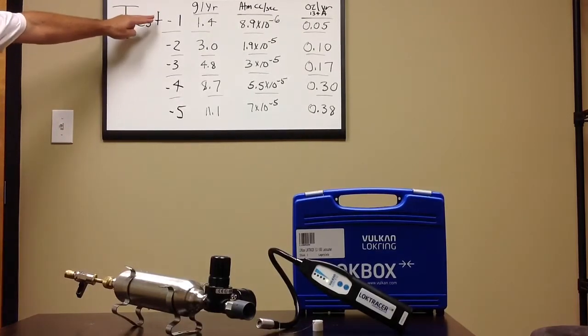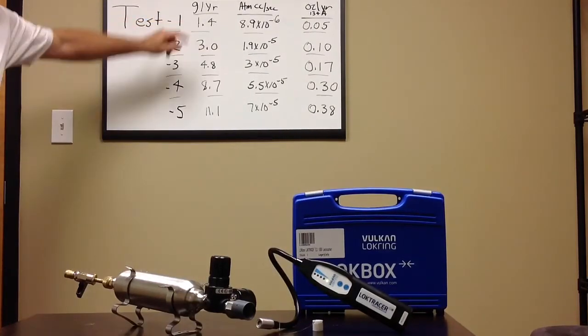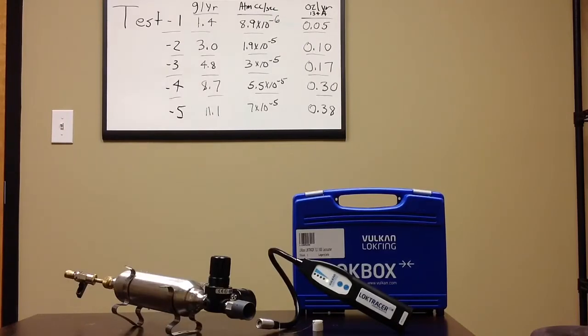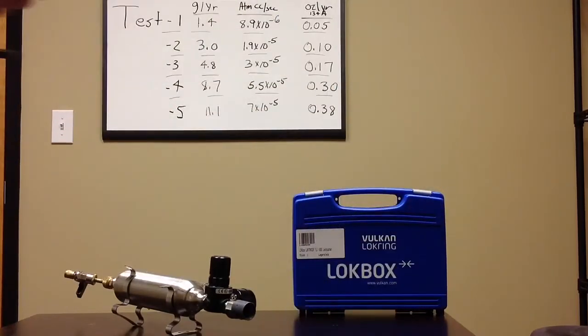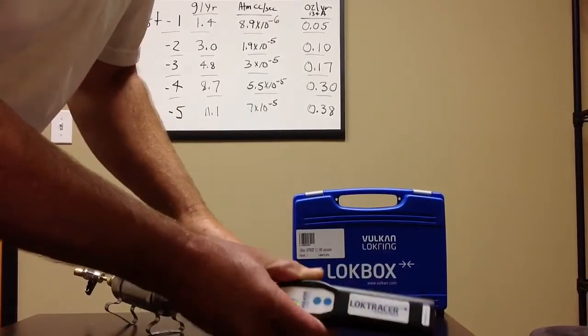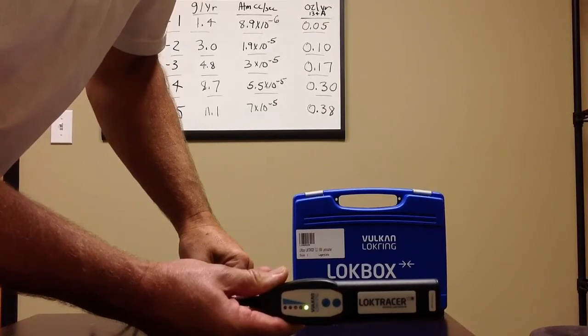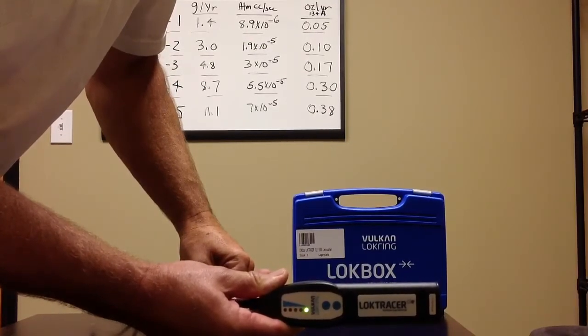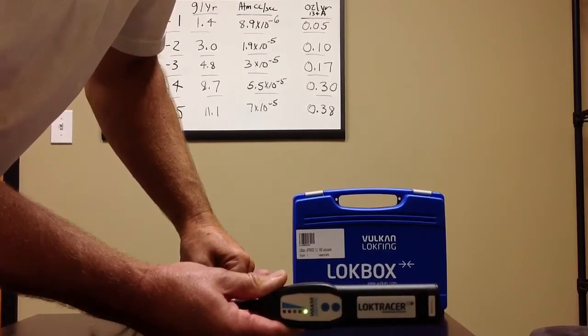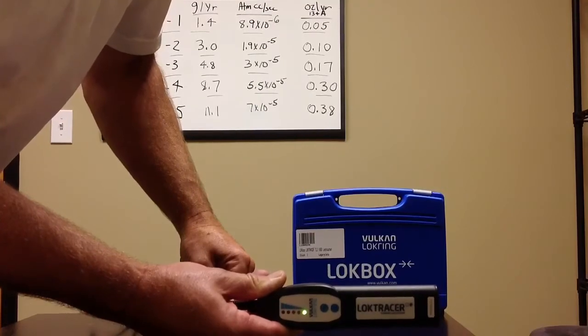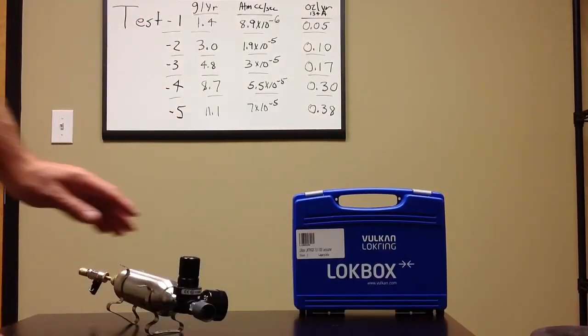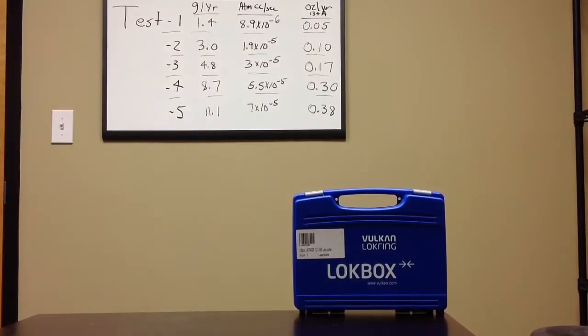So the first test point I have the leak set for is 1.4 grams per annum. So I'm going to show you the signal we would get with that. It's a very small leak, a little bit of a signal there. So you can detect it, but like I said, it's a very small leak.